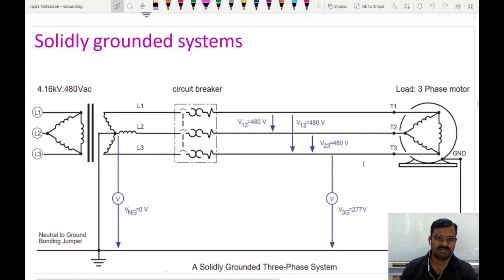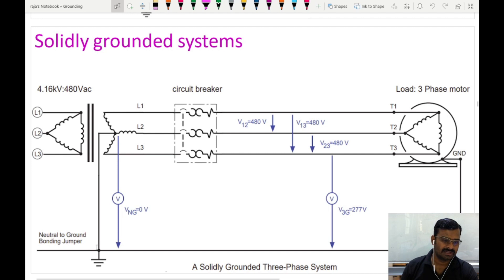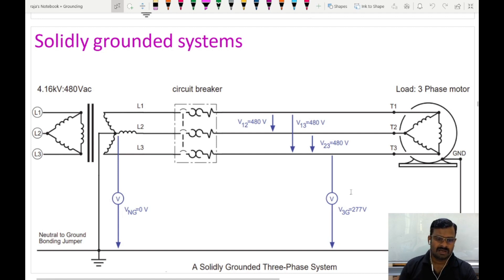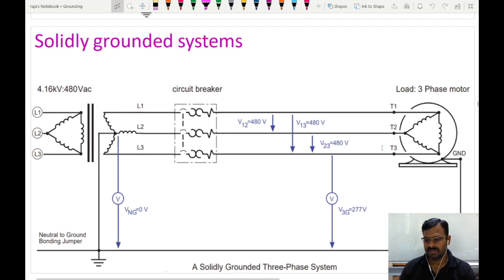This is how the solidly grounded system will look like. On the star connected side or secondary side, we have a neutral point connected to the earth with a pure conductor, and this conductor will have very high conductivity or very less resistance. On the load side, we have a delta connected load and the system is connected to equipment grounding — the metal casing of the machine is connected to ground. In a normal operating condition, the voltage applied in the three-phase system is balanced and the current flowing through the three different phases is of equal value.